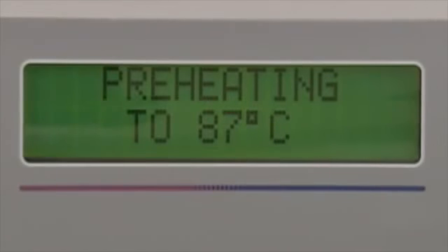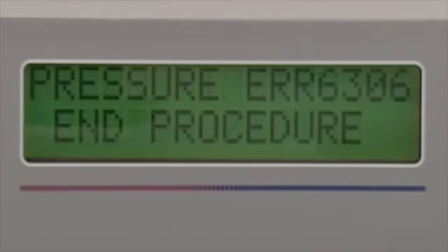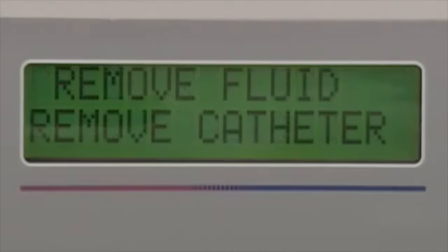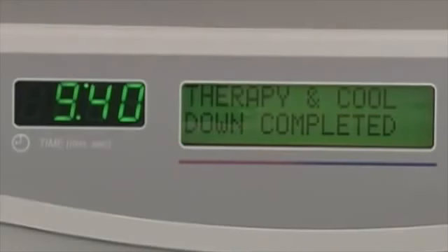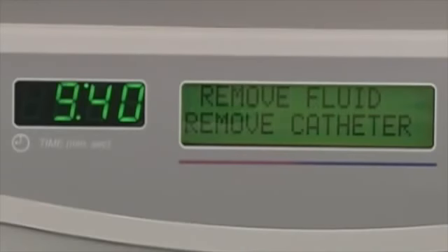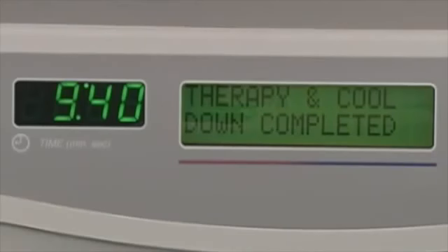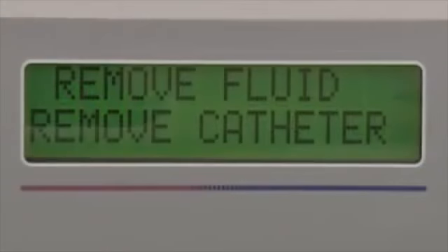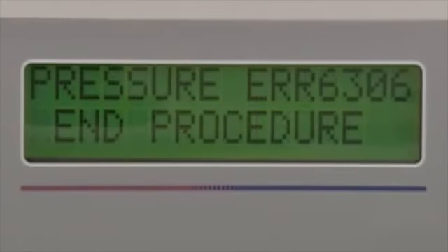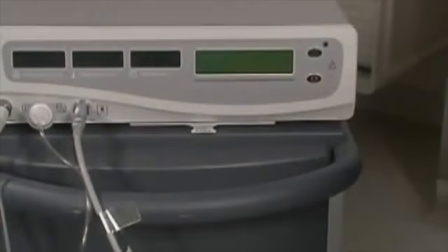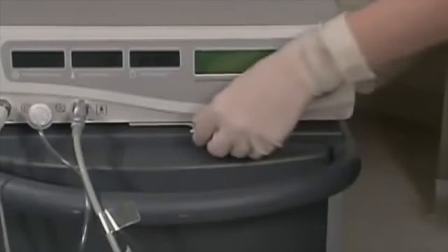Before beginning a procedure, you should become familiar with the controller's error messages and prompt codes. The message prompts guide you through the procedure. Successful completion of one step will trigger the next one. The error codes alert you when a problem occurs. Please consult the user manual for a complete listing of these codes. Additionally, for quick reference, a user card which pulls out from underneath the controller allows you to review the key steps necessary to perform the procedure.